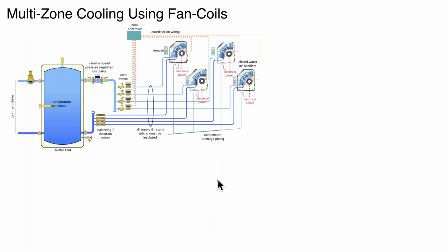Now, here's a pipe setup that is generic, but it shows what would be necessary for, let's say, a 4-zone cooling system using some type of air handler. I'm showing a wall-mounted console. Typically, there'd be a remote that would turn it on and turn it off. You're going to have to bring wiring from that unit, and typically it's going to be low voltage wiring, but you have to coordinate the operation of that unit with the balance of the system. So you're going to need low voltage cabling coming back to some type of zone controller. You're going to need supply and return for the coil.